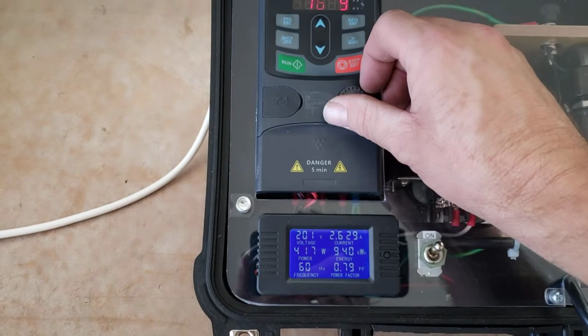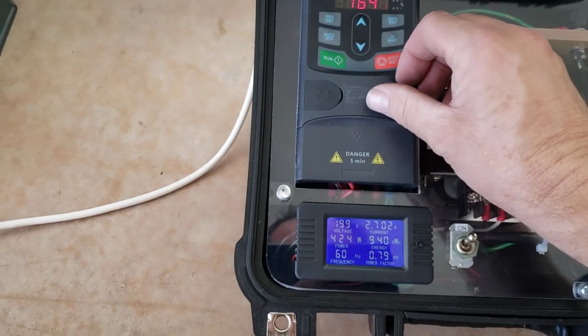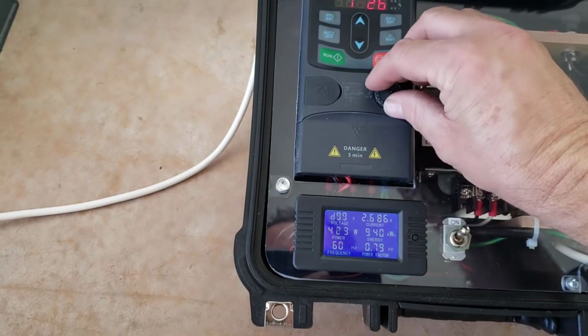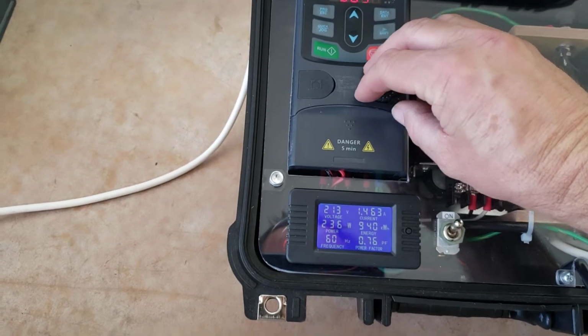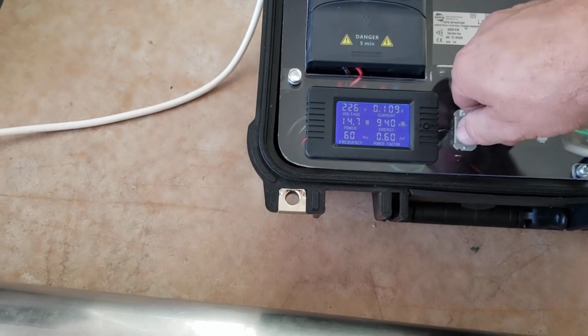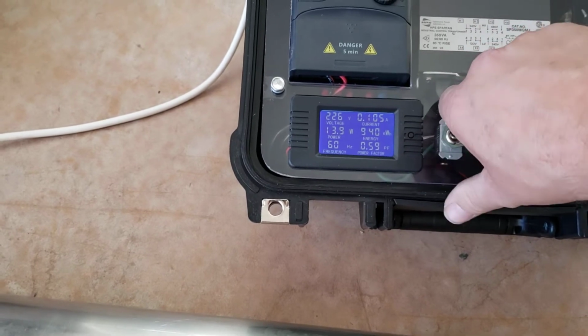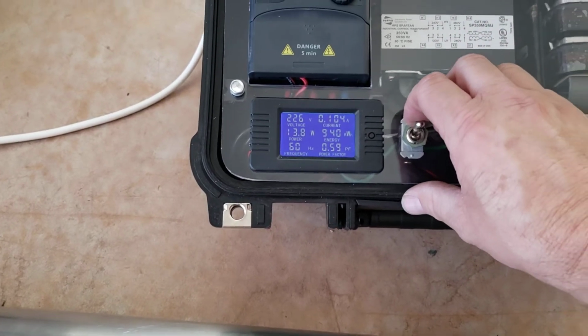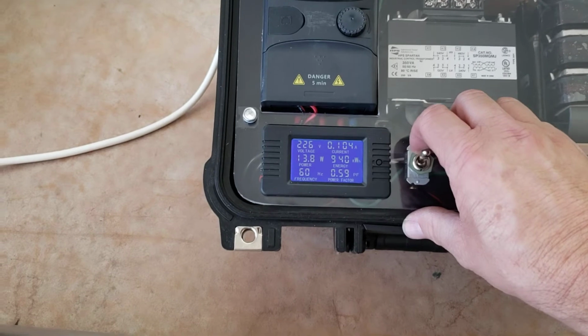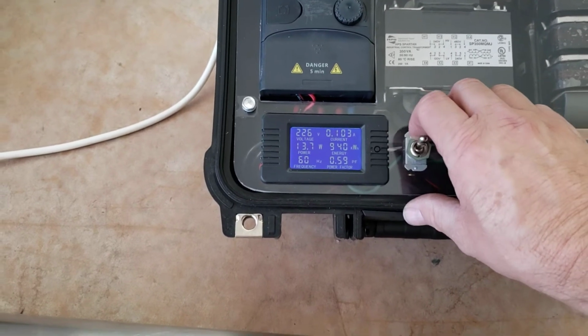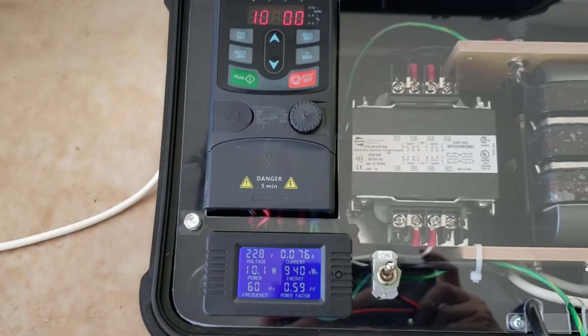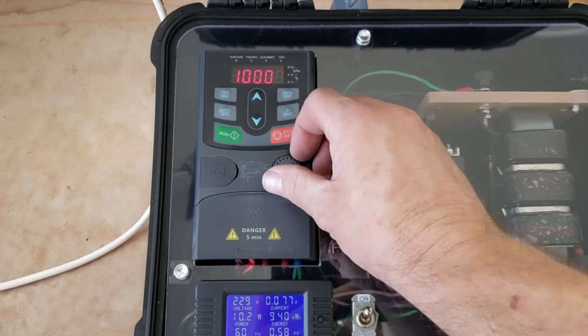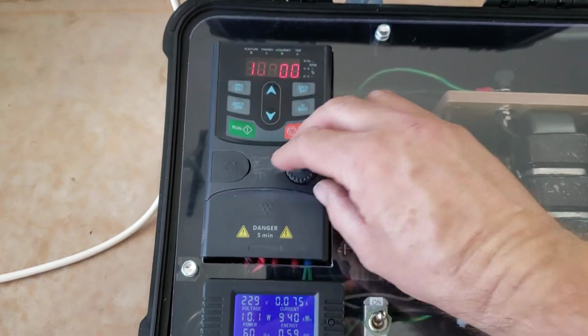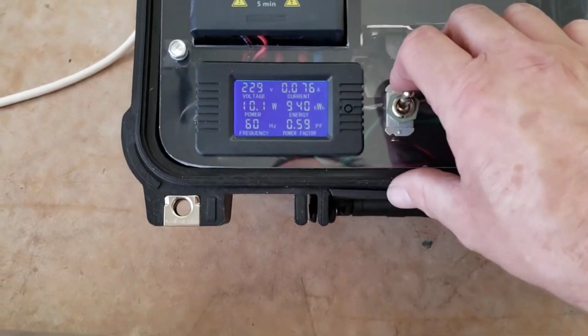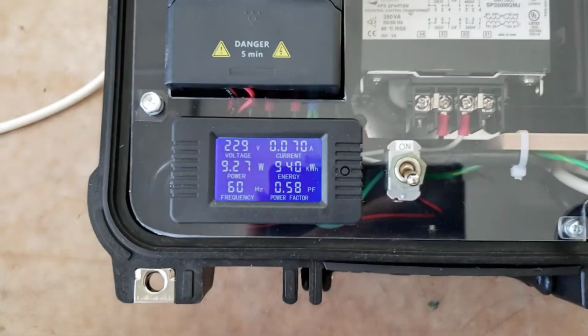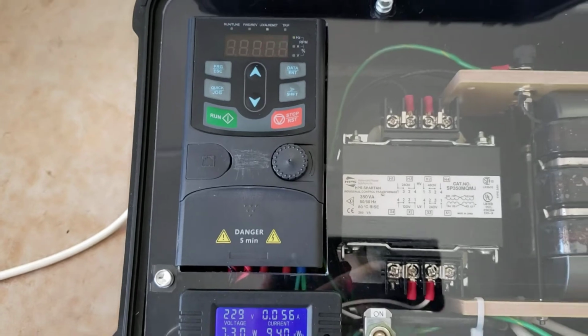Now this cell might need to be purged a little bit longer, but that's a normal cell. You get stable frequency and a stable wattage up around 400 watts. It should not jump around and oscillate the frequency like that other cell did, and you don't hear the arcing. And as before, when you're done with the test, turn the potentiometer counterclockwise to turn all the way down, and then switch off the power switch to shut off the high voltage.